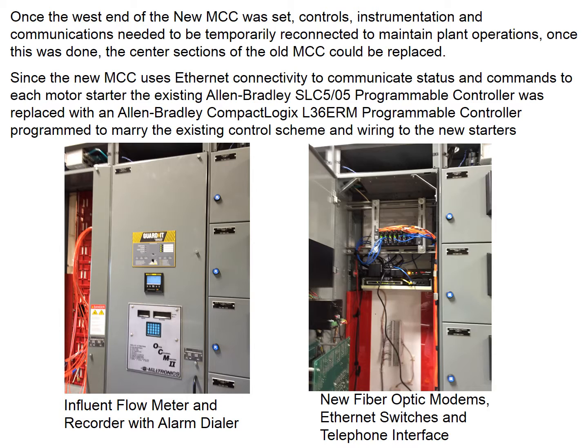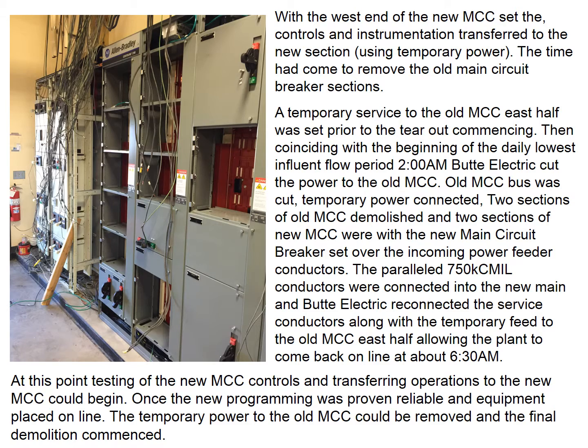Since the new motor control center uses Ethernet connectivity to communicate status and commands to each motor starter, the existing Allen Bradley SLC 5/05 programmable controller was replaced with an Allen Bradley CompactLogix L36ERM programmable controller programmed to marry the existing control scheme and wiring it to the new starters. With the west end of the new MCC set, the controls and instrumentation transferred to the new section using temporary power, the time had come to remove the old main circuit breaker sections.